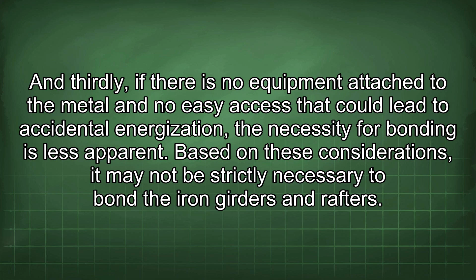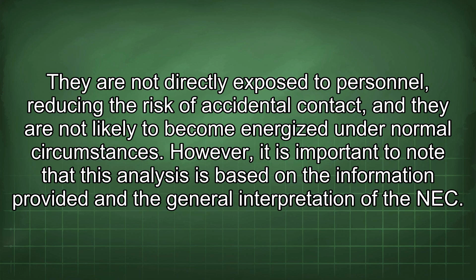Based on these considerations, it may not be strictly necessary to bond the iron girders and rafters. They are not directly exposed to personnel, reducing the risk of accidental contact, and they are not likely to become energized under normal circumstances. However, this analysis is based on the information provided and the general interpretation of the NEC.